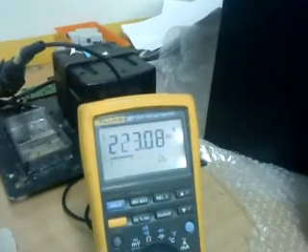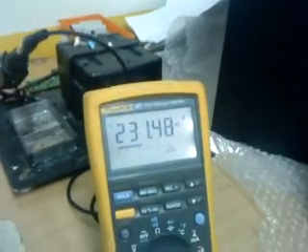And the output voltage also is increasing. So what you see here is that as per the 0 to 10 volt DC signal, the output voltage and frequency increases. And the load current also increases.